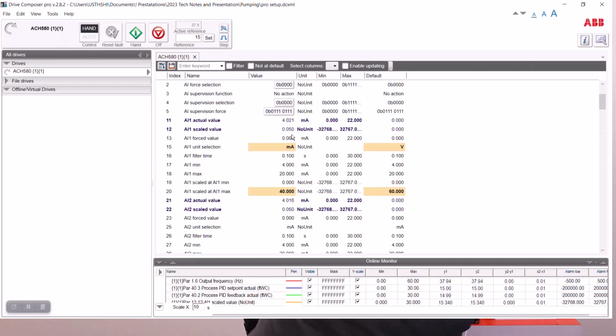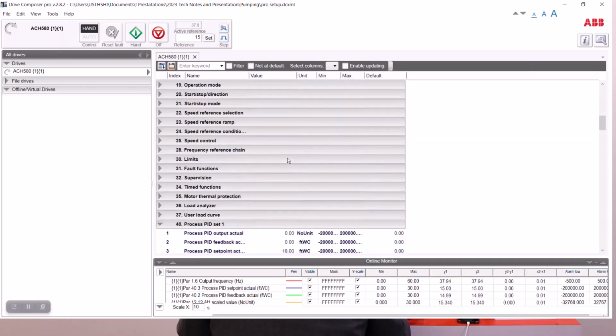When I look at the meter, it's saying 0.007. So it's a decimal point. It's a slight bit off, not enough to make any difference, because my input milliamp value is 4.02 milliamps, not 4.0 milliamps. So it's a tad bit off, not enough to make a difference for what we're doing here.